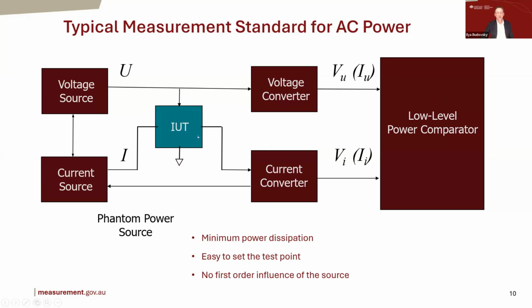So using the phantom power source obviously minimizes the power dissipation. There's no hundreds of kilowatts, it's just units of watts maximum that are dissipated in the measurement circuits. That's quite clear. It's also clear that it's easy to set the test point. We can just adjust the voltage and current independently using very stable sources, and we can adjust the phase angle between the voltage and current. And there's no first order influence of the source on this measurement.